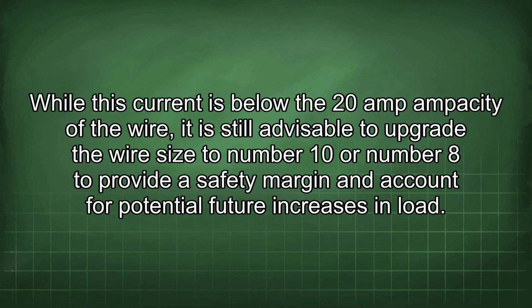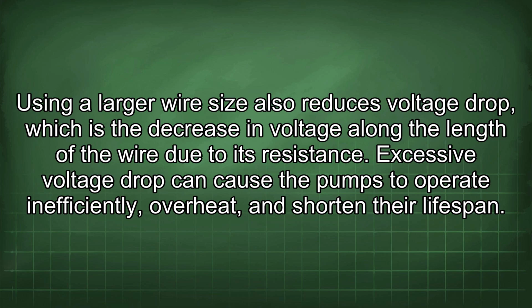While this current is below the 20 amp ampacity of a wire, it is still advisable to upgrade the wire size to number 10 or number 8 to provide a safety margin and account for potential future increases in load. Using a larger wire size also reduces voltage drop, which is the decrease in voltage along the length of the wire due to its resistance.